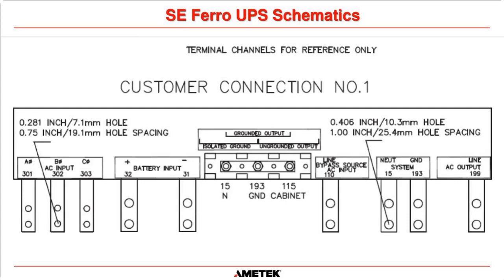So now the AC output. So this is what you connect your load circuits to. Okay, so this is going to be your live or line output, and then you would connect your neutral here. Okay. And if you're running 3 wires out to the load and you're running a ground as well, that is where you would connect your ground cable. So these are for your load circuits.